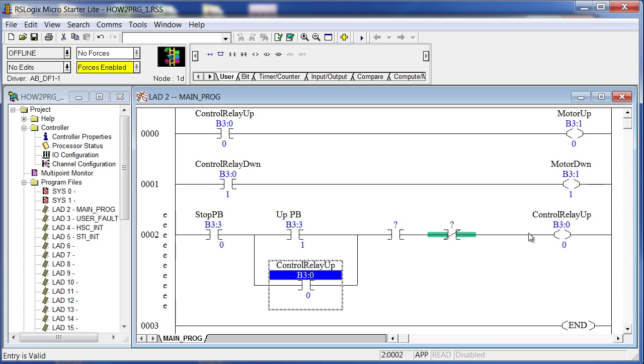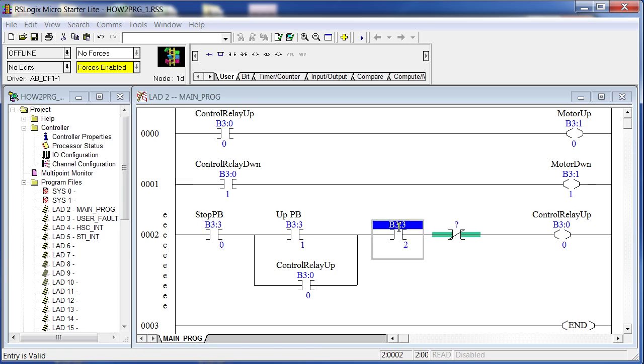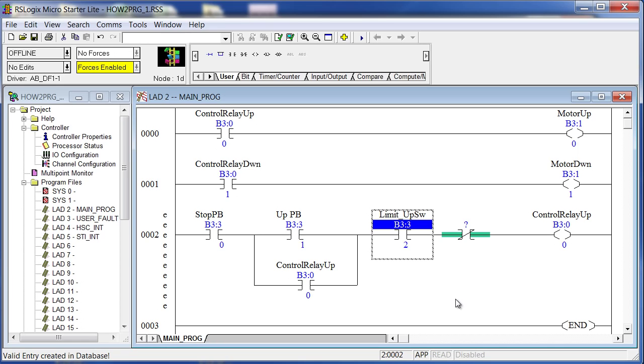Also, these three devices — if this were a relay coil, these would be normally open contacts of that relay. Now this is a limit switch, so we'll let this be B3:3/2 — 'Limit Up Switch.' The next contact is from the next rung's relay, which we haven't built yet. I'll Ctrl+C and Ctrl+V to duplicate the rung. This is the same stop button — same memory location. But this is the down button, so it needs the next unused location.